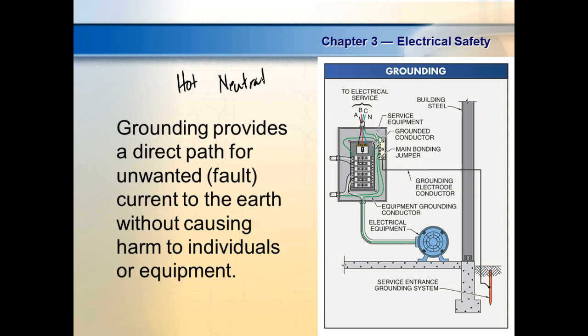Another thing is that we've got these metal cabinets, and I bring two wires in it, and I don't reference it to anything, and something happens, and the wire shaves, and that black lead gets on the outside metal of your thing. Instead of that metal cabinet on your refrigerator being a cabinet, it's going to be a conductor now, right? You understand that? So what we need to do is figure out some way where we could prevent any metal thing from becoming electrically hot or electrically charged. So what we do is we ground the neutral. So the neutral inside your panel box is connected to earth ground. So NEC calls it the grounded current carrying conductor.